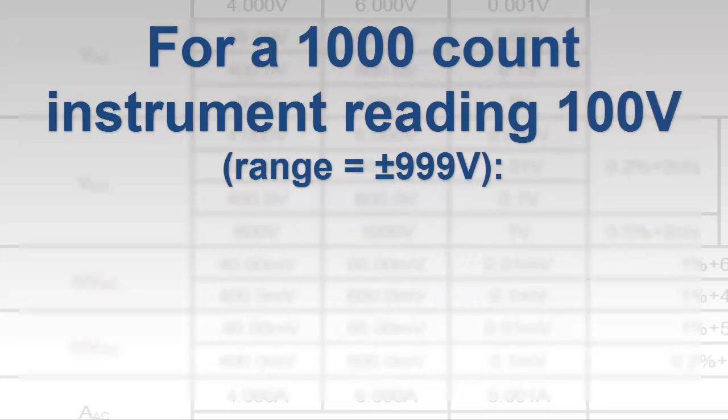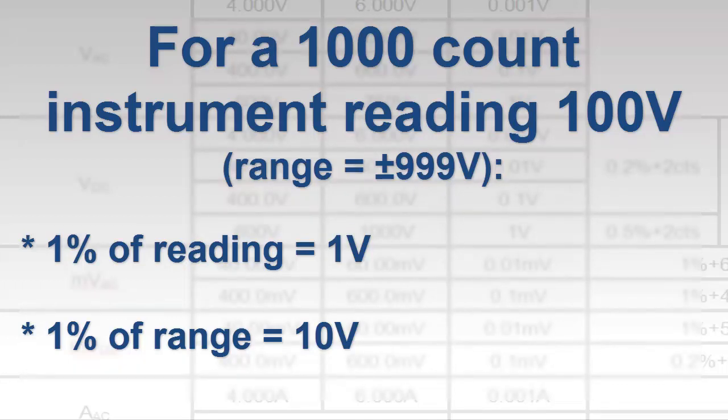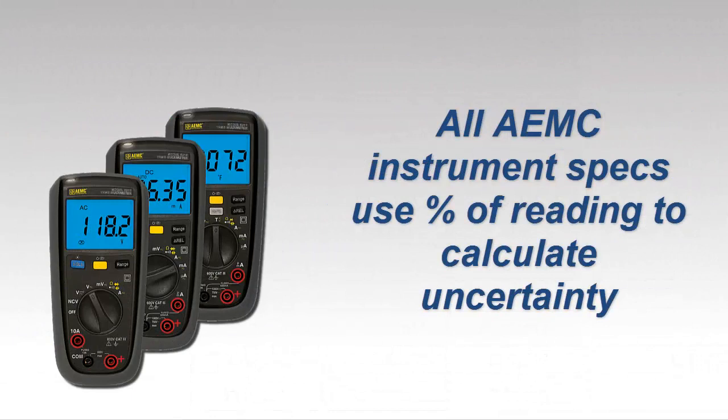For example, consider a one-thousand-count digital multimeter displaying a reading of 100 volts. One percent of the reading would be one volt, while one percent of the range would be ten volts. So be sure to check whether the percentage applies to the reading or the range when comparing specifications of different digital multimeter models. Note that the uncertainty specifications for all AEMC instruments are always expressed as a percentage of the reading.